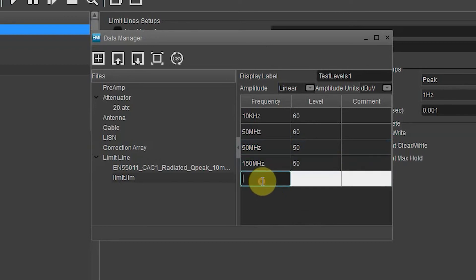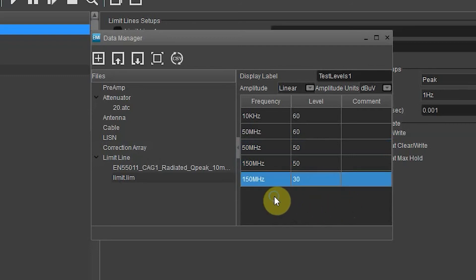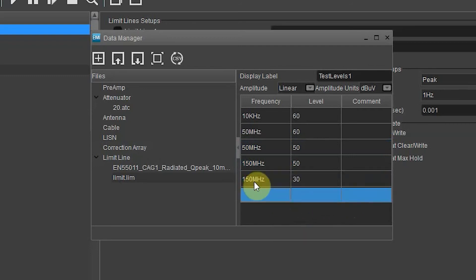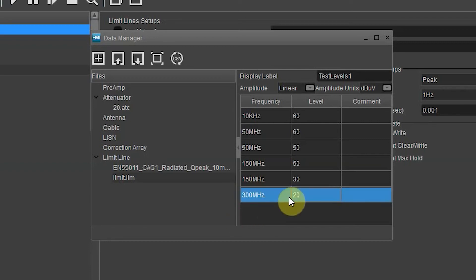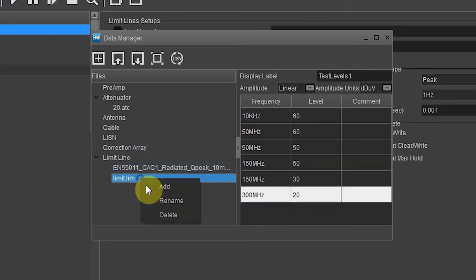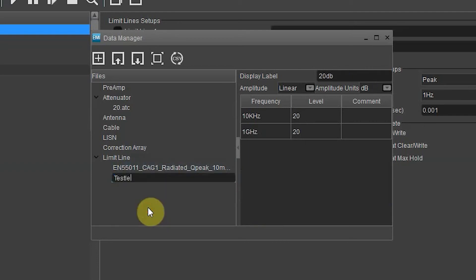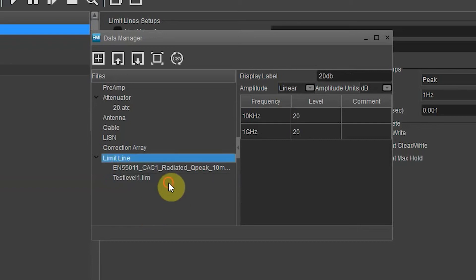Then let's do 150 megahertz at a 30 dB microvolt level and decrease it a little bit — going to 300 megahertz down to 20 dB microvolts, so you should see that line going down. All the data looks correct. This is ending and beginning the line, which is why you see it correlating that way — you start at 10 kilohertz and pick up at 50 megahertz where the last segment left off. Now let's go ahead and change the name to 'Test Level'.